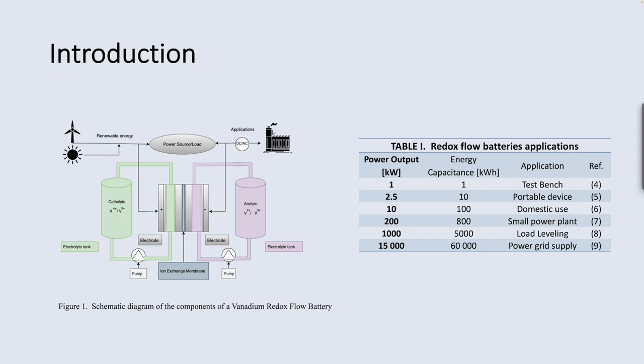The vanadium redox flow battery is an electrochemical energy storage system that stores energy in two electroactive liquids called anolyte and catholyte. These liquids contain dissolved vanadium ions in different oxidation states — vanadium 2+ and vanadium 3+ in the anolyte, and vanadium 4+ and vanadium 5+ in the catholyte — which are pumped through the battery cells separated by an ion exchange membrane. The vanadium redox flow battery consists of several main components, including the two electrolyte tanks, the electrochemical cell, the ion exchange membrane, and the pumps.